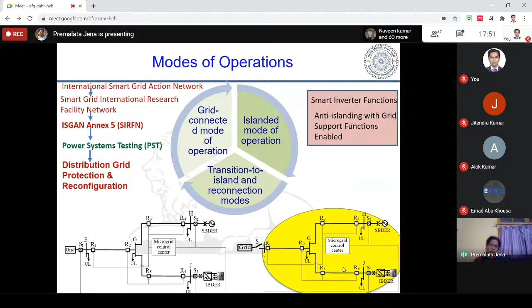These are some of the problems when we fail to quickly detect this unintentional islanding: out-of-phase reclosing, degradation of power quality, because when the microgrid is disconnected, inside it you have an active and reactive power mismatch.